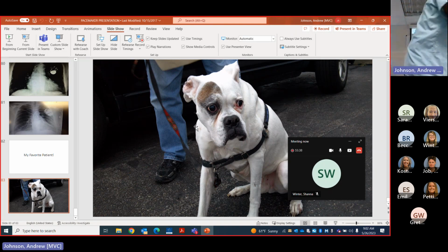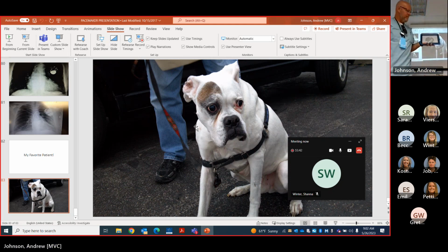So we're going to set this off to the side. Set it over the top of the pacemaker. And it's going to bring up, hey, is this what you want to pull up? Because they're wireless telemetry now. So it wants to make sure this is the only one here. So yep, it's got to be the right one. So I'm going to hit continue. It's saying it's getting signal from it. And it shouldn't take too long to download.